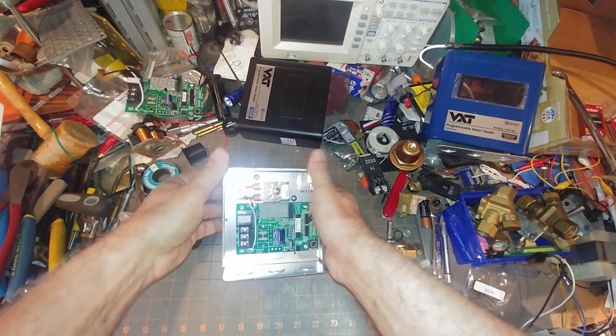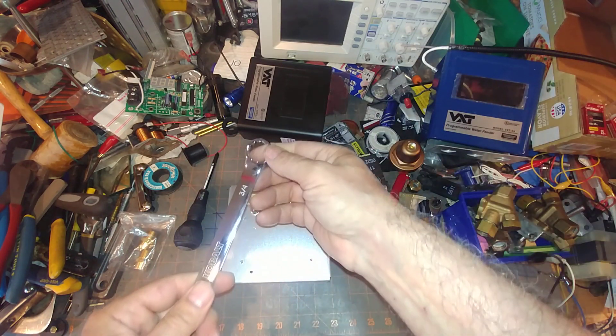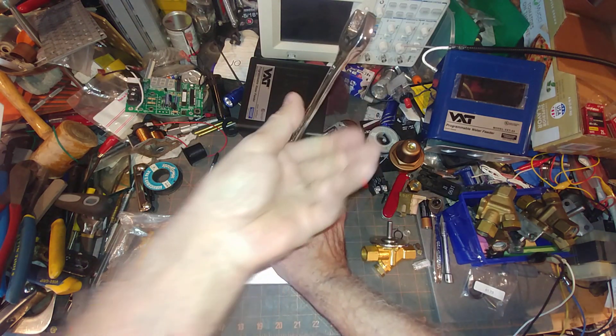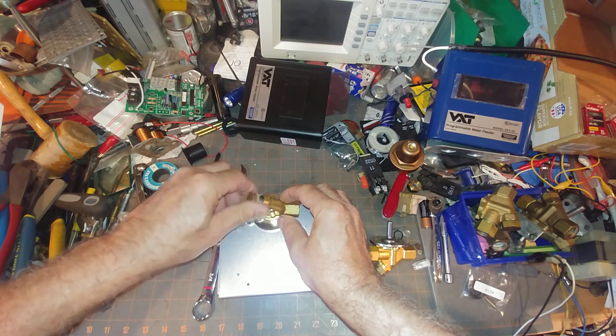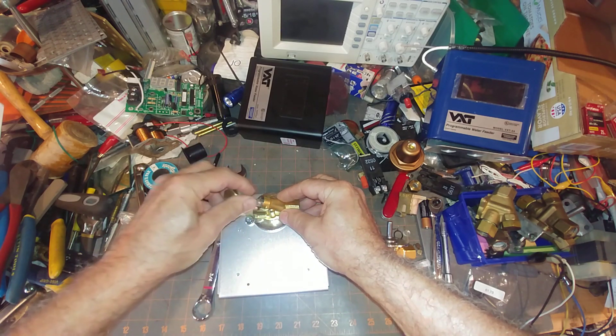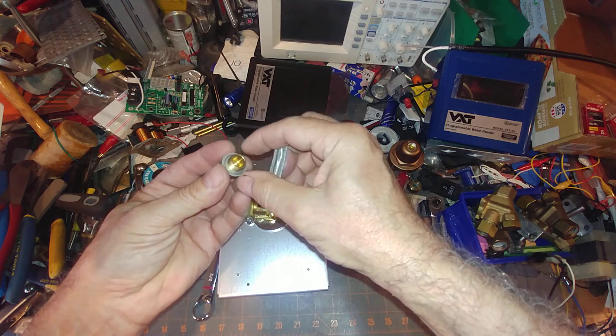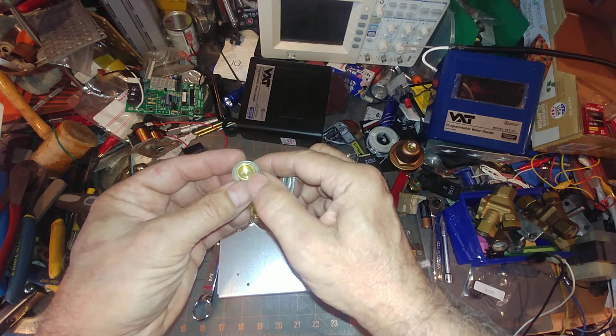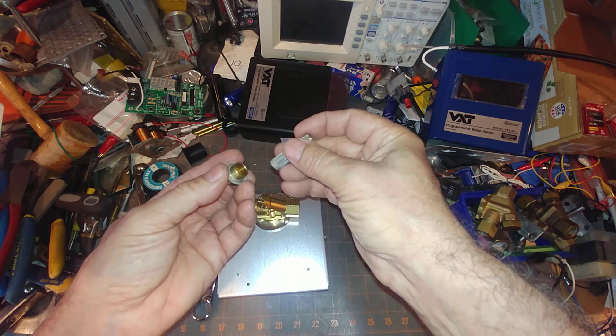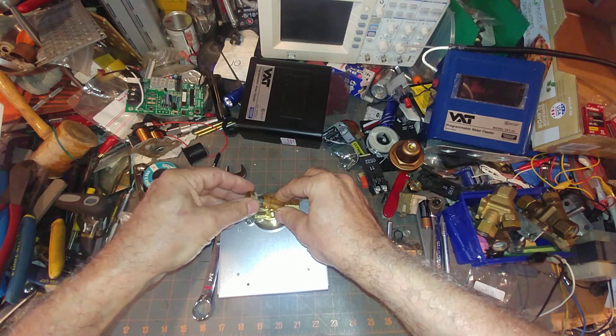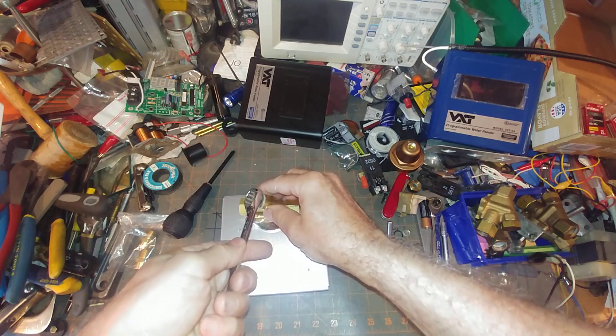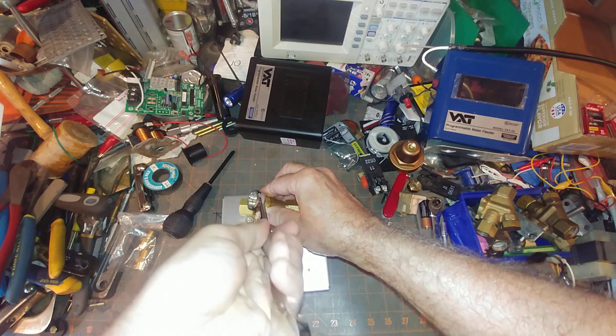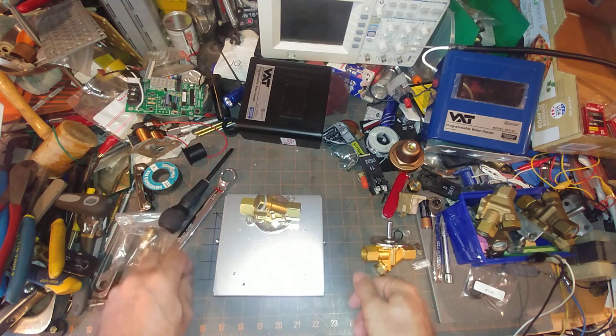They've also gone to great lengths to make the strainer easier to maintain. A three-quarter inch box wrench makes quick work of getting this apart and can take out the strainer, take this cover off. This is a very efficient strainer, less likely to let stuff go by. A weakness would be this gasket here, which is made of clear plastic, which I'm going to guess is polyethylene terephthalate, which might be brittle and might crack over time. So you don't want to crank on this. I'm hoping that my fears prove groundless on that. But I wouldn't crank on that any more than to stop the leak.